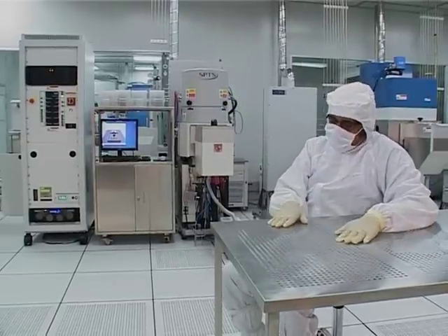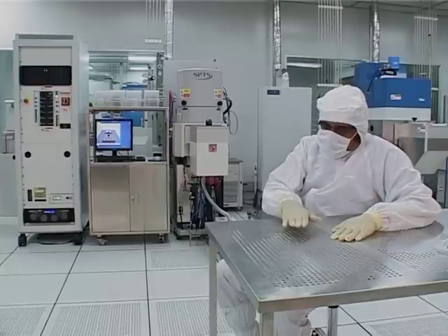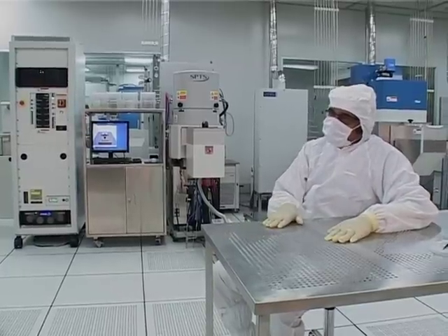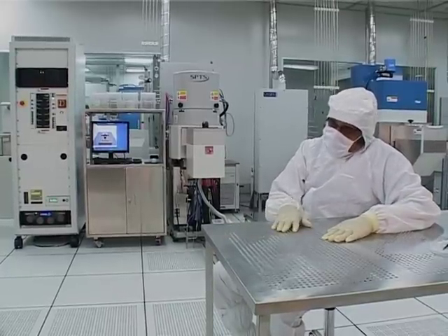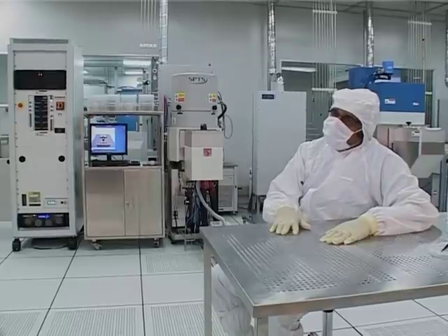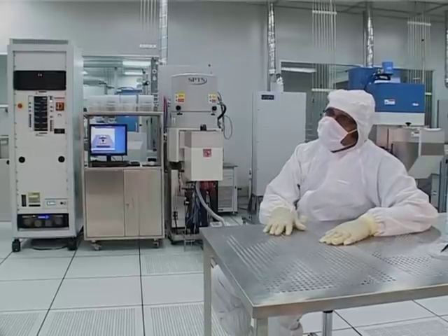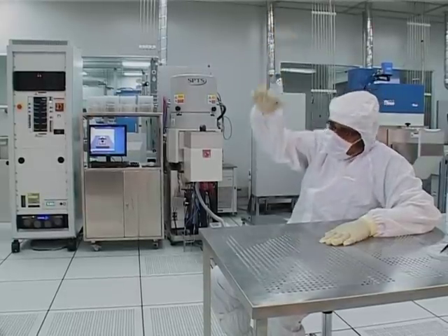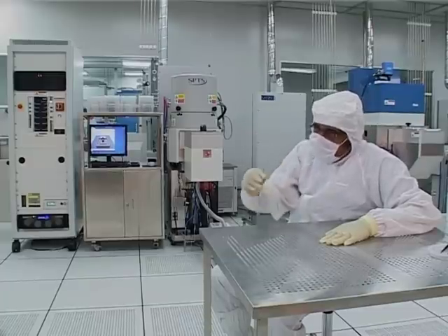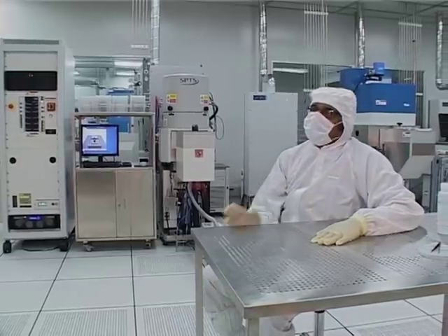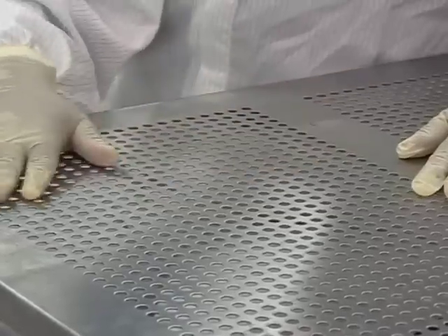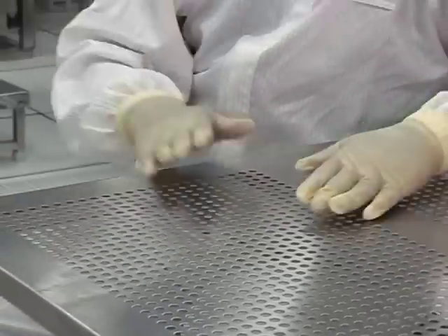Now I am sitting on a working table, and you may wonder why there are perforations on this table. These perforations are such that they will not alter the airflow pattern within this room. When the air comes here, it passes through this table and goes through the perforated tiles down. If there were obstacles, that would alter the airflow pattern.